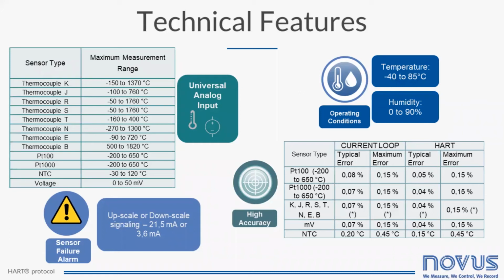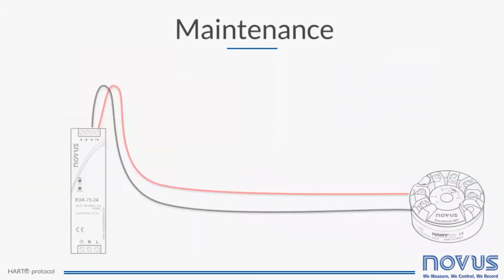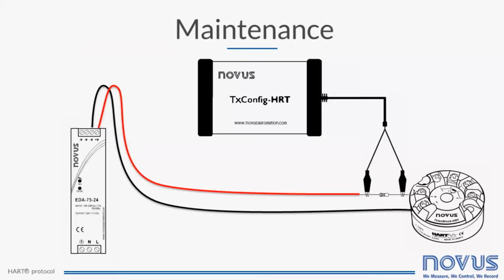For these transmitters, the operating conditions are temperature from -40 to 85 Celsius degrees, or -40 to 185 Fahrenheit degrees, and relative humidity from 0 to 90%. The installation of a HART device is the same as any other 4 to 20 milliamps device. The only difference is that communication is made over the current loop, requiring no additional or special cables. The same cable that provides power will also provide access to HART device settings.